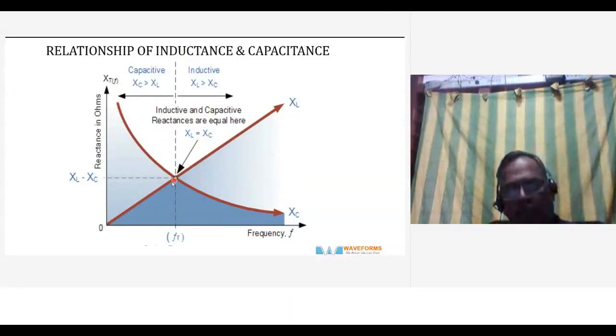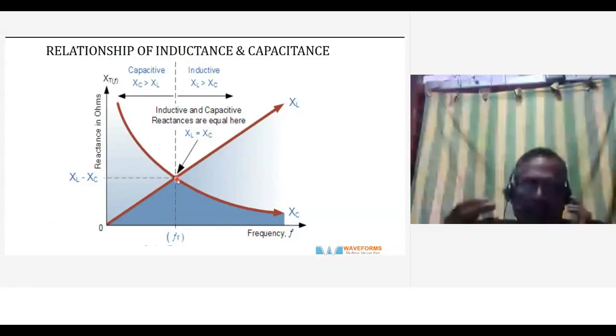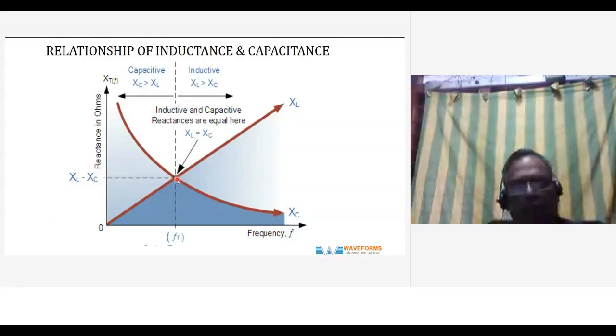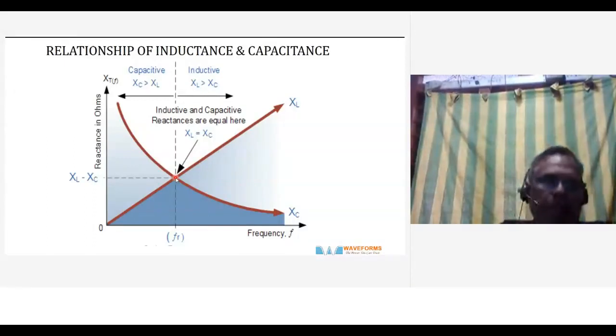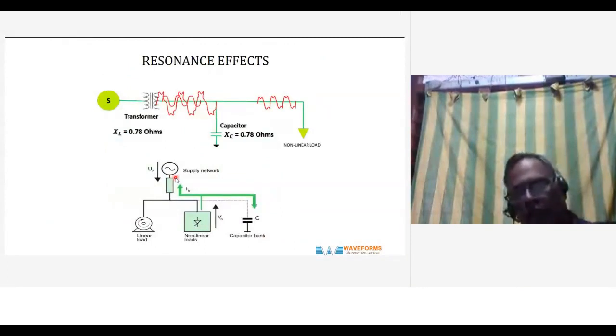So this is a serious problem in a network which is rich in harmonics. It will be capacitive when XC is more than XL. But when XL, the inductive reactance, is more than the capacitive, it becomes inductive. So this is how we manipulate and try to create a low impedance path for the harmonics. So it has a dual effect. One adverse effect of resonance is this problem.